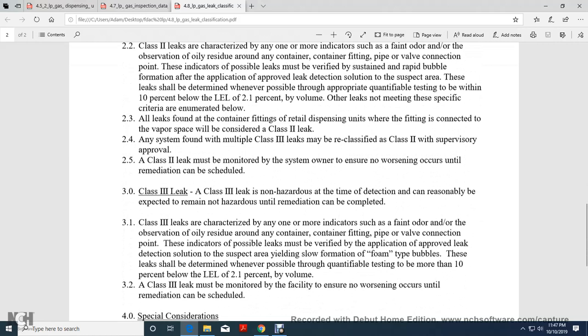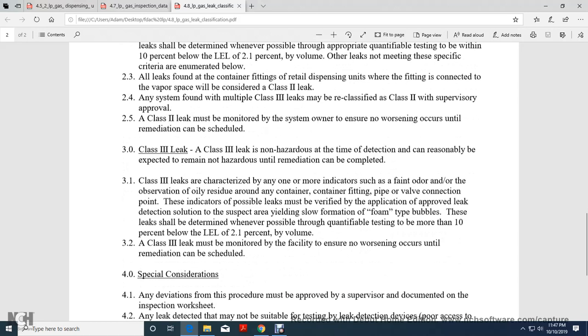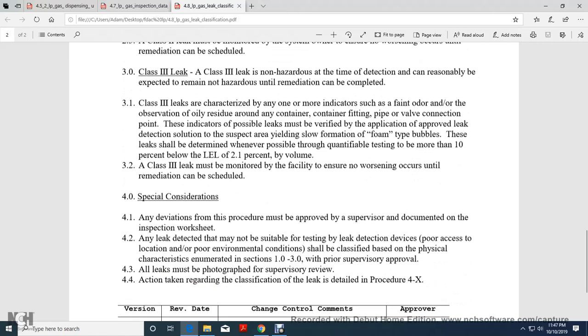All leaks found with a container fitting of the retail dispensing unit with a fitting connection of the vapor side are considered Class 2 leaks. A system found with multiple Class 3 leaks may be reclassified to Class 2 with supervisor approval. Class 2 leaks must be monitored by the system owner to ensure no worsening occurs before remediation can be scheduled.